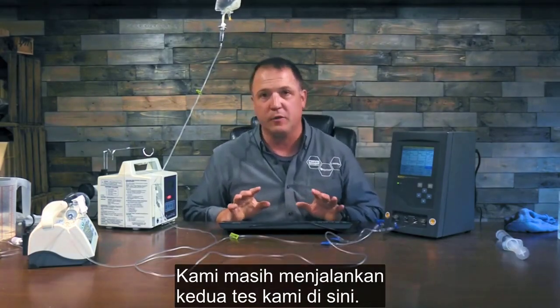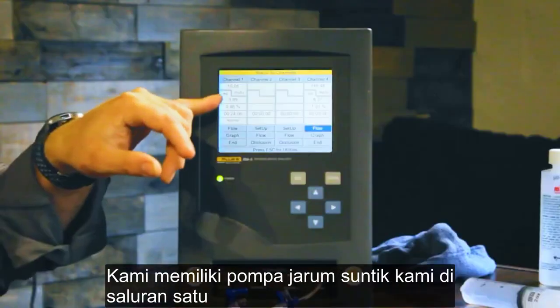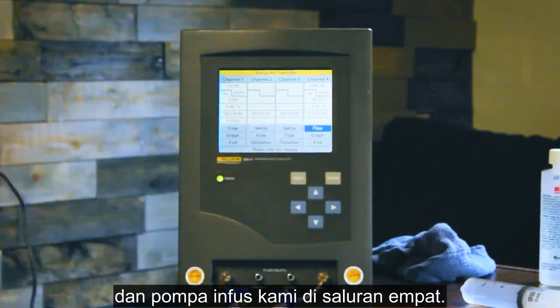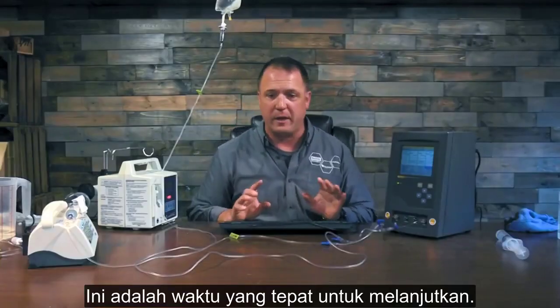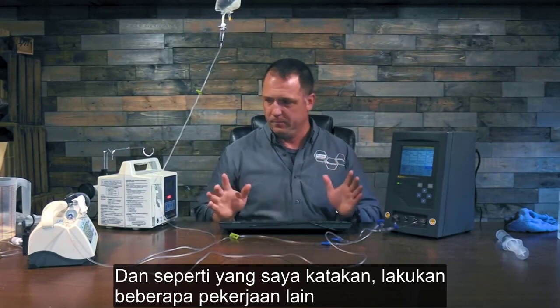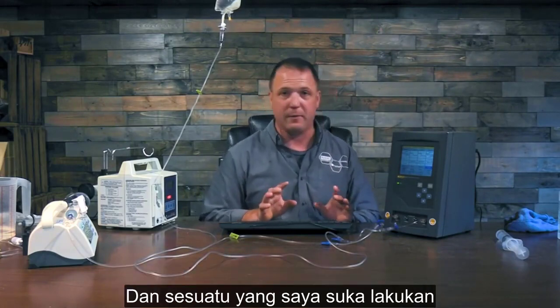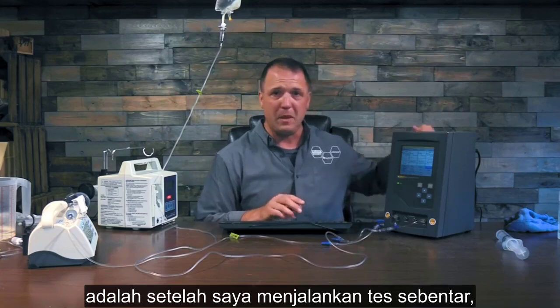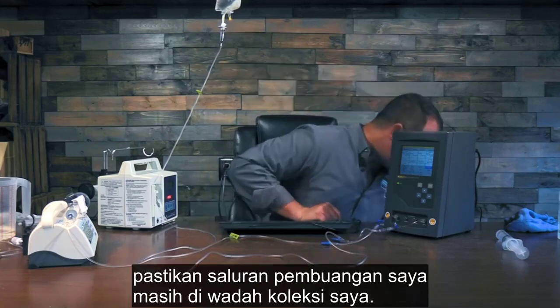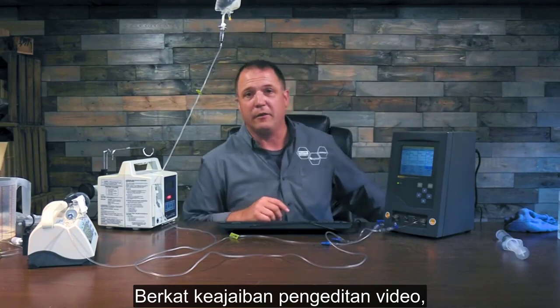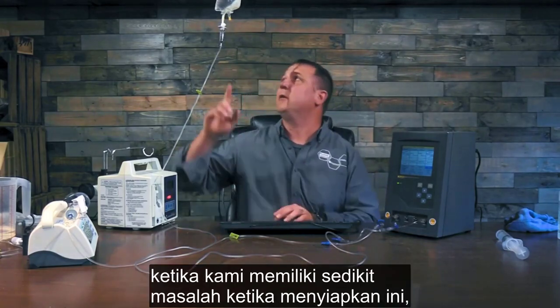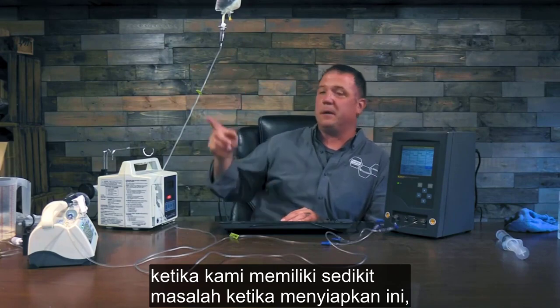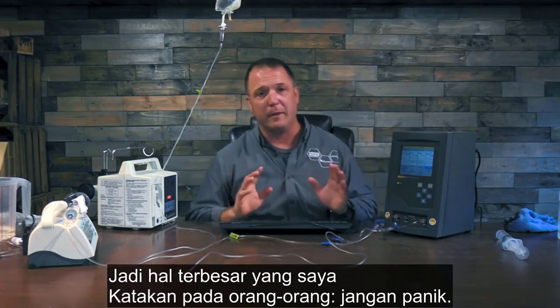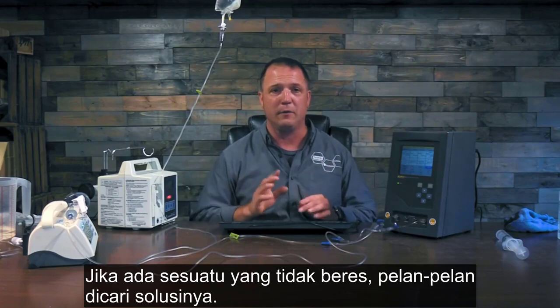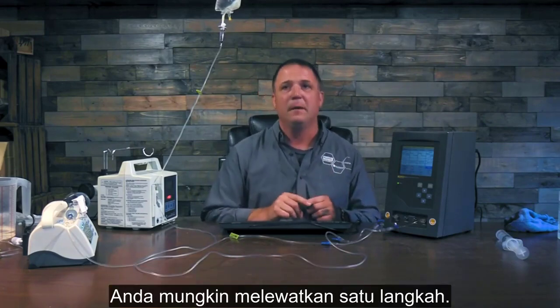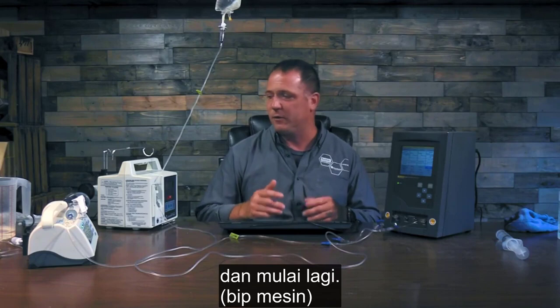All right, we're back. We're still running both of our tests here. We have our syringe pump on channel 1 and our infusion pump on channel 2. This is a great time to go ahead and, like I said, do some other work that needs to be done on the bench. And something I like to do is, after I run tests for a little bit, make sure my drain lines are still in my collection device. Thanks to the magic of video editing, you don't get to see the mistakes other than when we had a bit of an issue getting set up here, but it's going to happen in the field. So the biggest thing I tell people is don't panic. If something's not going right, slow down. You probably missed a step. Go ahead and reset, look at it again, and start again.